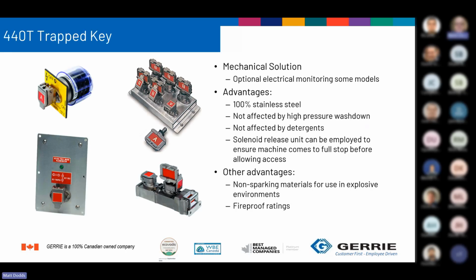So first, trapped key. This has been around a long time, designed for electrostatic precipitators that use a high voltage. So if someone was trapped in there and the power was turned on, they wouldn't exist very long. So these were designed so that the operator could go in there, work on it, come out, lock the door before the power was turned back on. So they're a 100% mechanical solution.